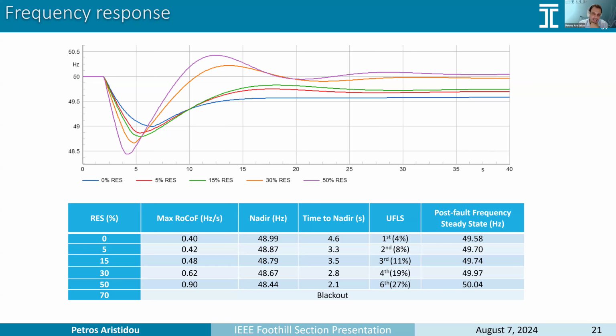No, it's not, because in this case, for fast frequency response, we don't consider grid forming converters. So usually the response time, as in the grid code now, is 600 milliseconds. And the initial RoCoF that we measure is during the first 500 milliseconds. So by the time that the battery activates and starts providing support, it does not really affect the RoCoF during the initial period. Of course, it affects the RoCoF later on. If we have grid-forming technologies, which can activate in 5 milliseconds or less, then of course the battery can also impact the RoCoF of the system.